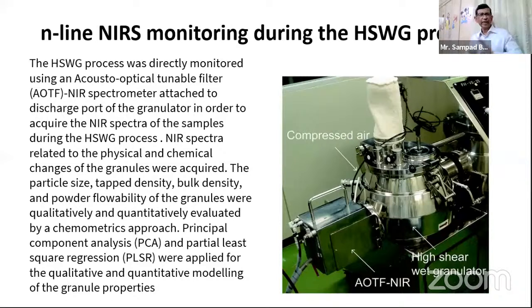This is an example, a kind of case study, using an acousto-optical tunable filter, AOTF, NIR spectrophotometer. Here, in this case, you can read, and I will explain that the NIR is not a probe. It is a device mounted on the discharge end of your granulator. Acousto-optical, because there are different kinds of NIRs. There are diffuse reflectance and dispersive. Acousto-optical is the mechanism of generation of the pure NIR beam.